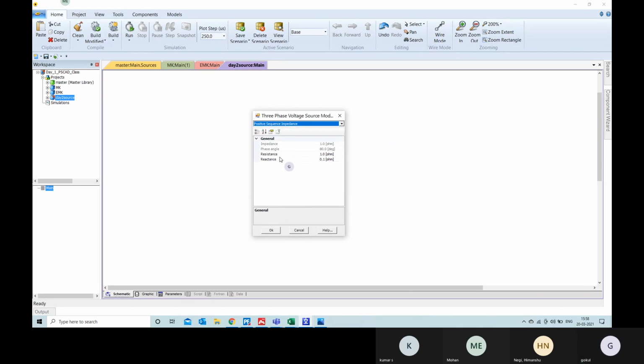So in PSCAD, the units are a bit tricky, and you have to follow this unit. So you cannot give in micro ohm or milli ohm. Like if it's an ohm, just try to give it in ohm itself. Don't take that risk. If you want, you can just add an M, like it will be milli ohm or something like that, but don't take that risk. Just give as it is. If it's asking ohms, if you get the value in micro ohm, convert to ohm and give it. So that thing you have to be cautious on. If you're working in PSCAD, that should be a small tricky part.